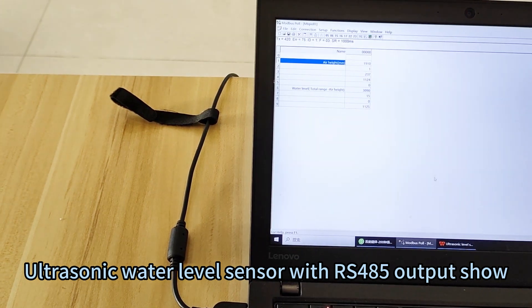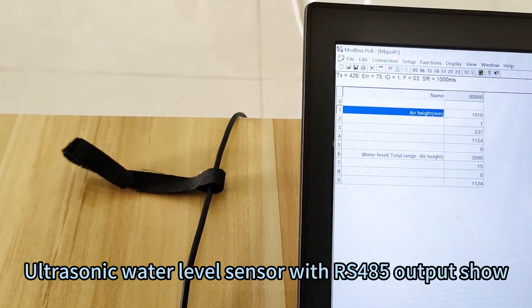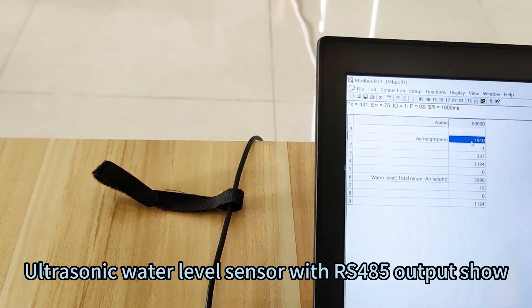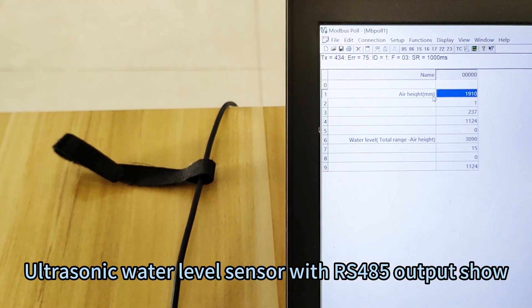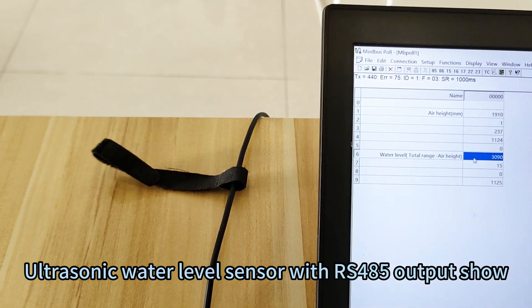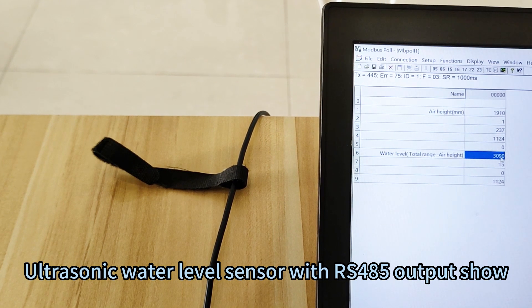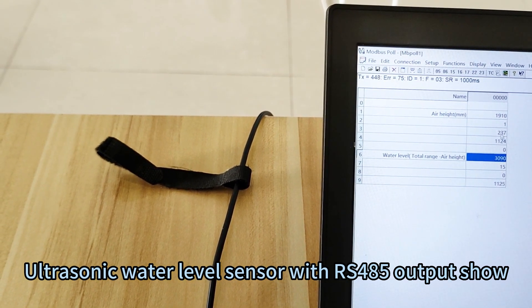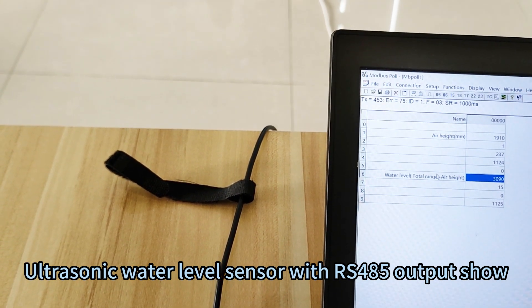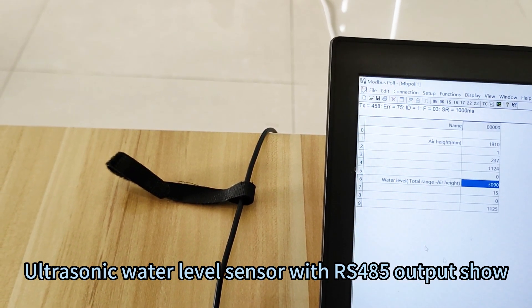So we will check the software. This software is used for ModBus RS485 ModBus server software. At present, the air height is 1910 mm and the total height is 5000 mm. So the water level equals total range minus air height, which is 3090 mm. That is the server software — I will send you the software so you can test it directly on the PC end. That is the basic introduction.